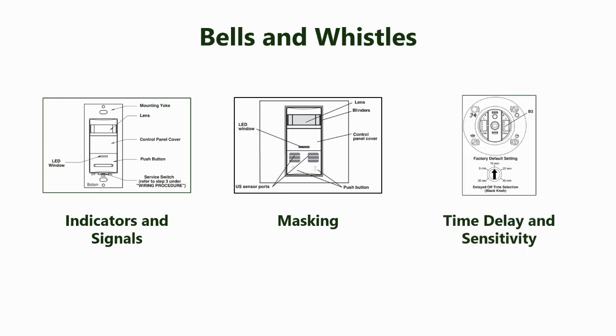Time delay is the amount of time after a lack of detection before the sensor turns off, and sensitivity is the ability to detect motion at a distance. These features may be adjusted at the sensor or remotely via laptop or tablet. If done at the sensor, this is usually accomplished using dip switches and sometimes an additional dial.